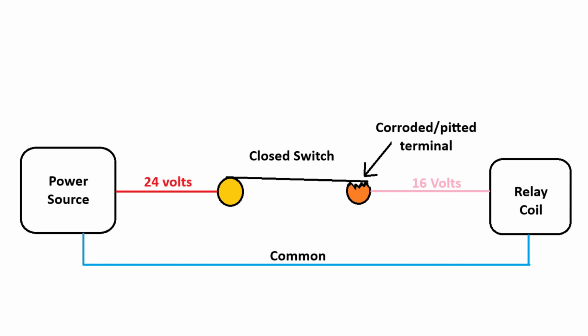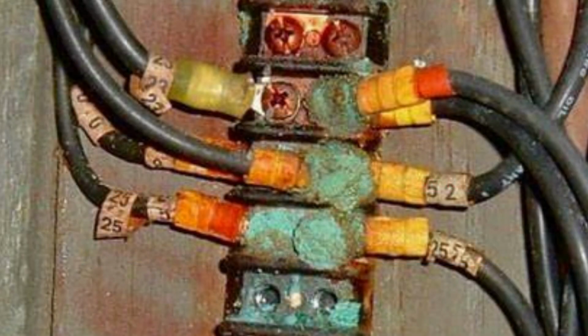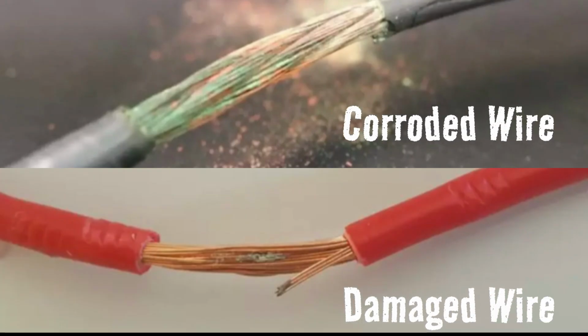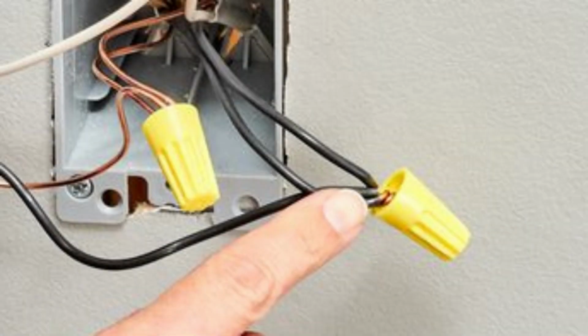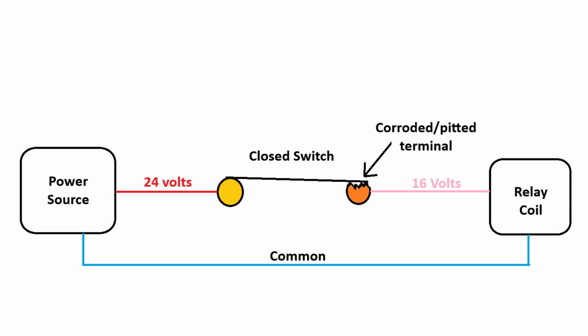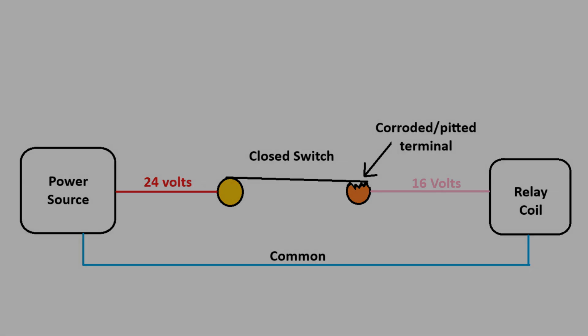Now, these voltage drops could be caused by corroded and pitted terminals. They could be corroded wires themselves. Sometimes you just have to cut them back and restrip them to fresh copper. Sometimes it's caused by loose wire nut connections. I mean, basically, you're looking at the integrity of all connections and terminals through this circuit, looking for these sorts of voltage drops.